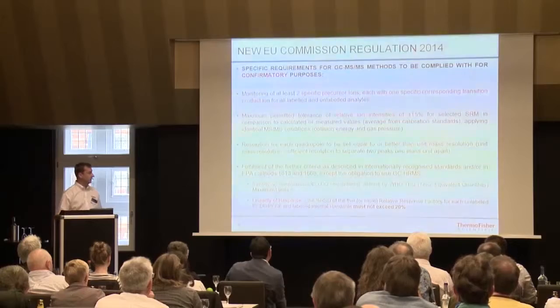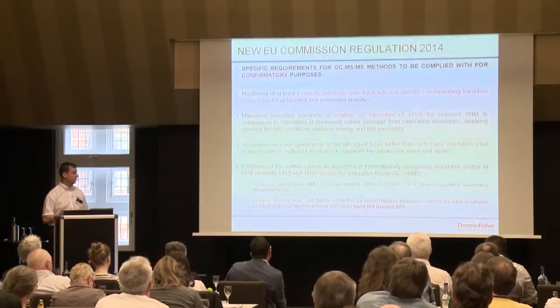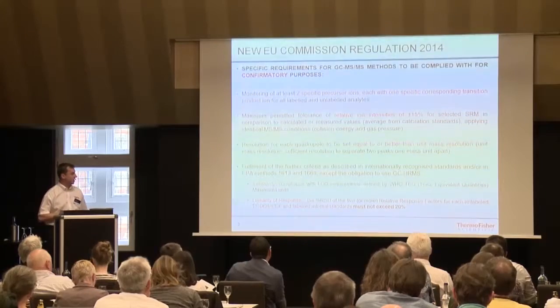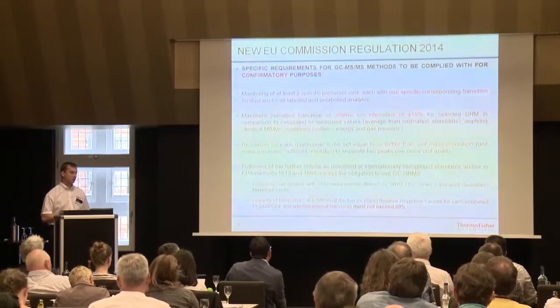The third point, equally important, is to have unit mass resolution on the quadrupoles on the system we're running the samples on, or better obviously. We also have to fulfill further criteria as described in methods like 1613 or 1668, except the obligation to use GC high-resolution MS.